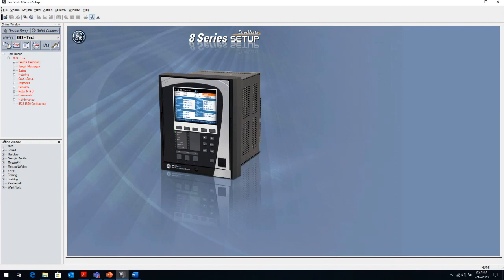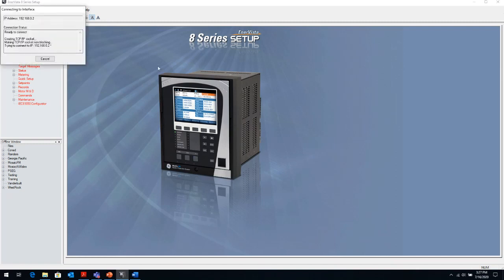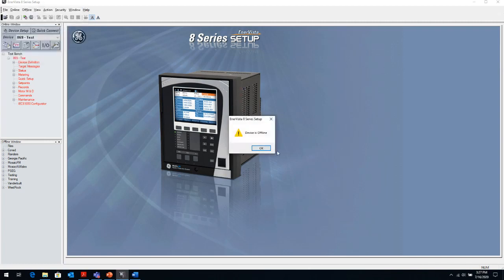And you'll notice there are a bunch of icons on the top. The first icon to the left is what we refer to as the sequence of events icon. And something is up on my relay. It's not communicating at the moment. Might be because I'm on the corporate network at the moment. So unfortunately, it knocks me out when I try to connect to the corporate network off of my local Ethernet connection. So anyway, the sequence of events icon is to look at the sequence of events in the relay and to see what is going on in the relay in real time. And usually if there's a trip, there's certain control functions going on in the relay. They will all be timestamped, show up in the sequence of events.